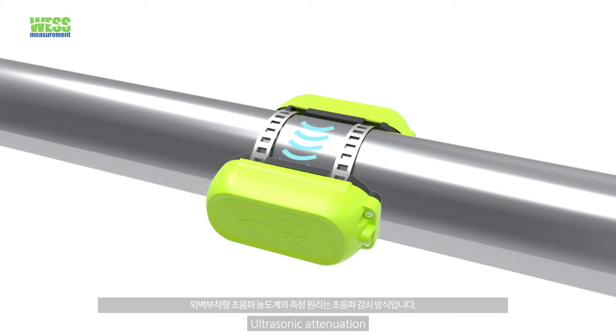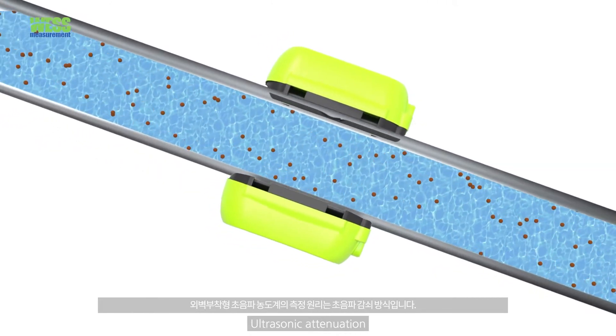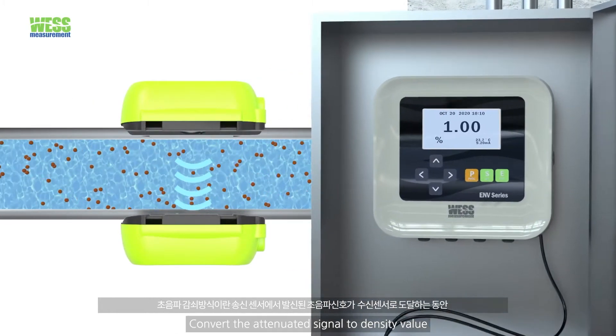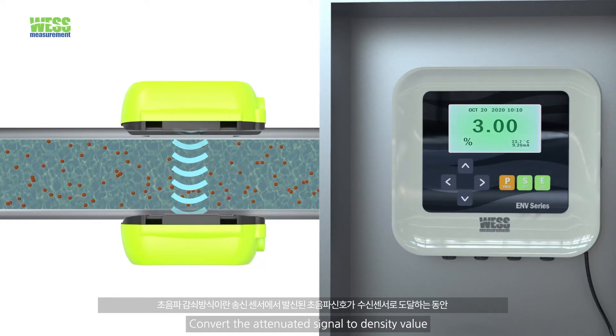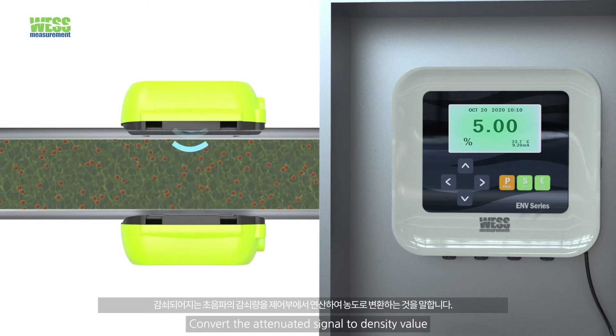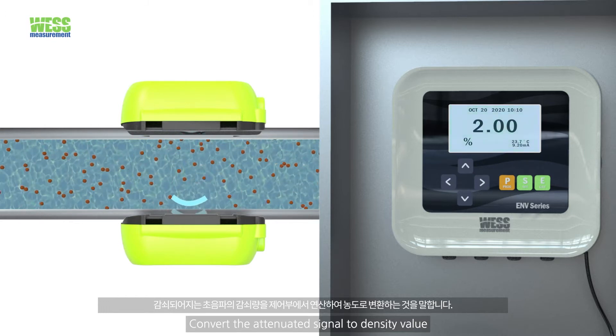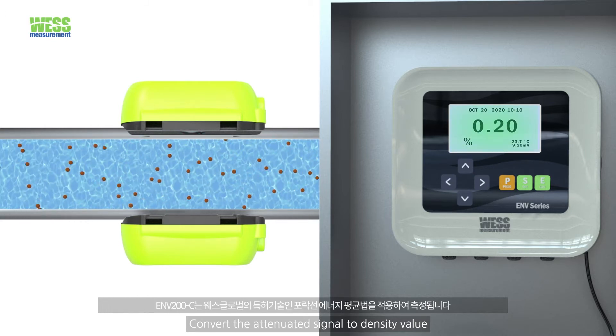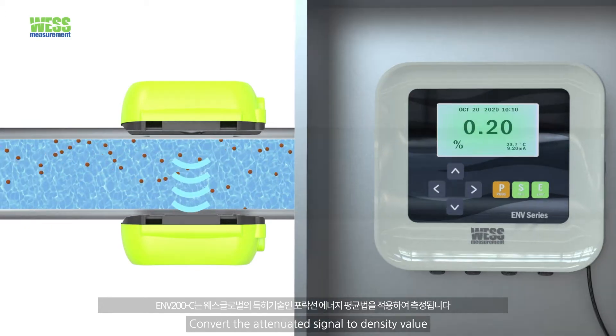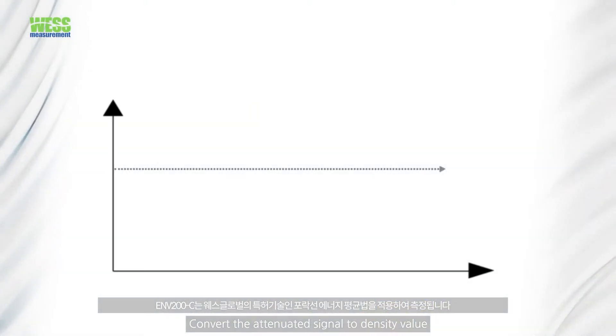The measuring principle of the density meter is ultrasonic attenuation. The ultrasonic attenuation method converts the amount of attenuated signal to a density value. This signal attenuation occurs when the transmission sensor signal reaches the reception sensor after sludge penetration. The ENV200-C clamp-on density meter applies the patented measuring algorithm EEAM — envelope energy average method.